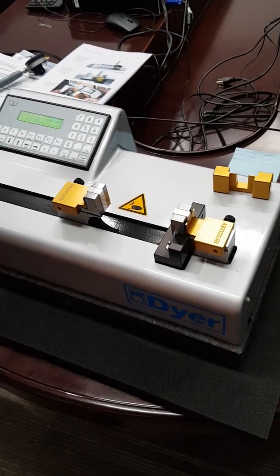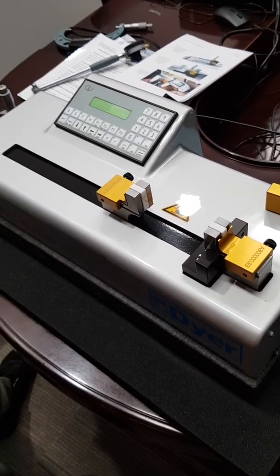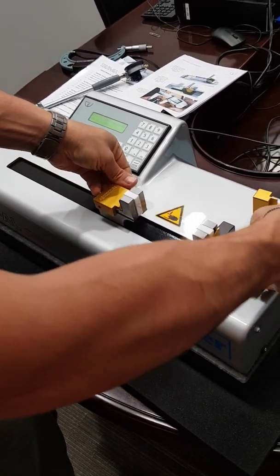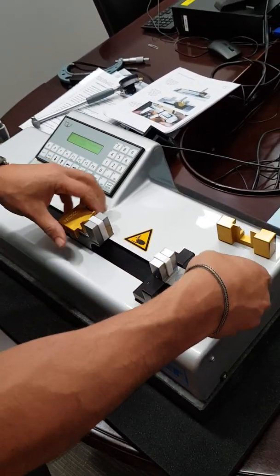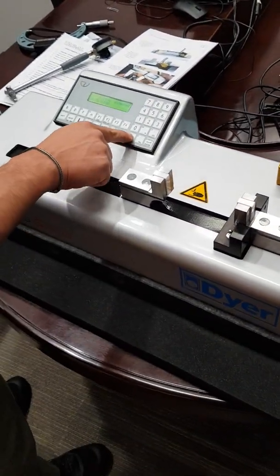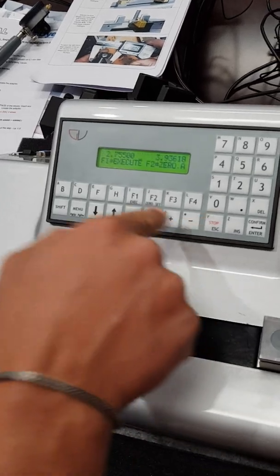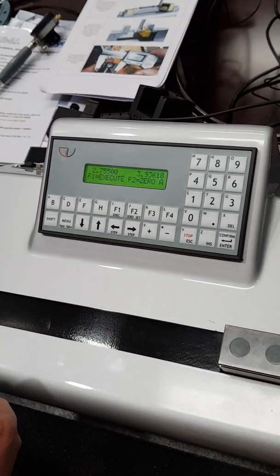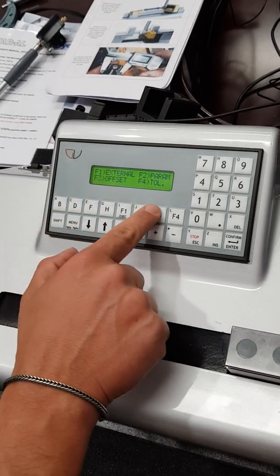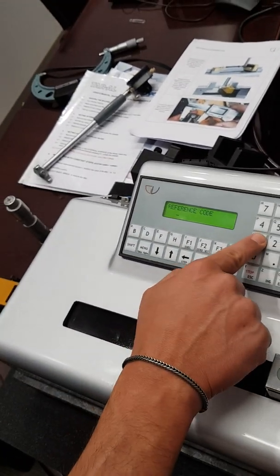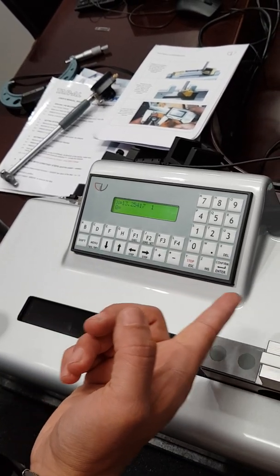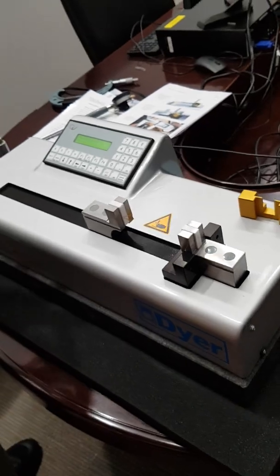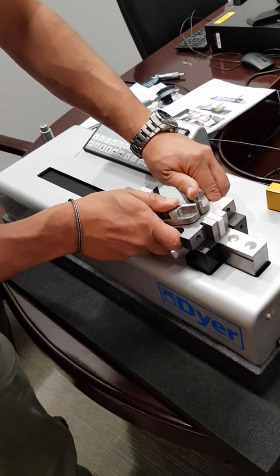So let's assume now we have to set up a three-point micrometer. We remove the adapter of the other instrument. We press ESC twice to go back on the standard function which is internal, and we press menu F3. Reference code is going to be one, enter, and the machine is now working with diametral values. We locate this steel adapter.